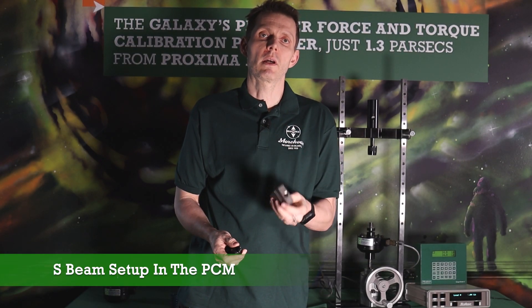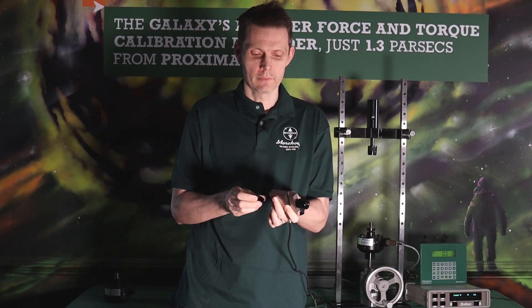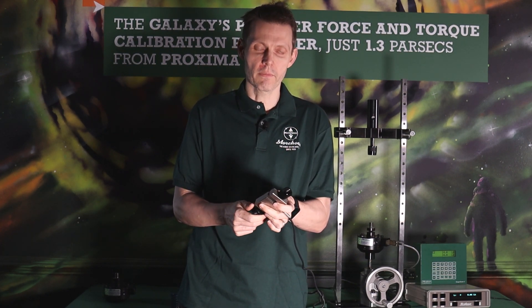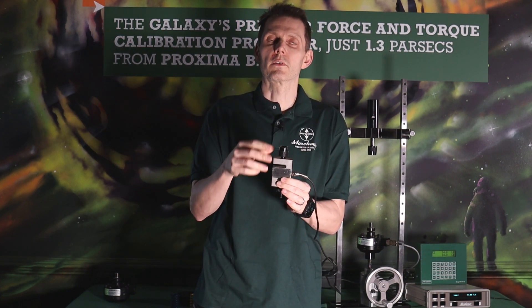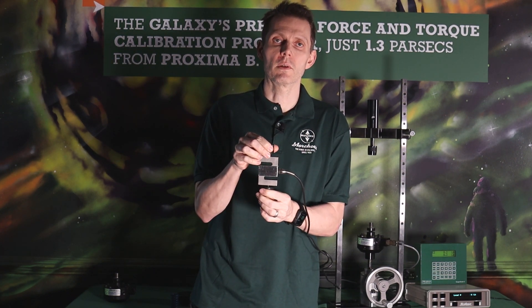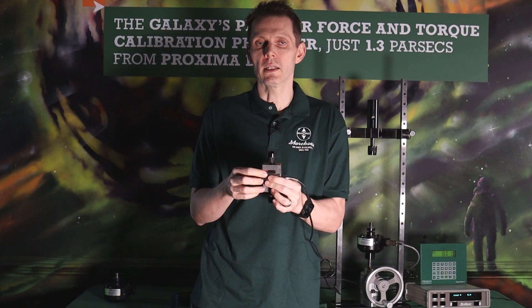We're going to go over setting up an s-beam in our portable PCM. We have an s-beam load cell here and we're going to thread the adapters in top and bottom. S-beam load cells are interesting in that depending on how I load this cell — both threads loose versus both threads tight — if they're loose in compression, I'm going to have very good symmetry. That means if it deflects negative 1.8 in compression, tension is going to be around 1.8.